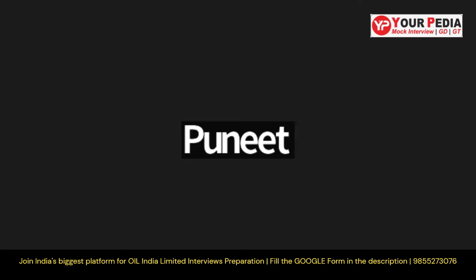Sir, first of all, I would see whether the voltage and current are within the permissible limits during the problematic condition. If they are, then I would tackle the problem, whatever is occurring. And if they are not, my first objective would be to disconnect it from the supply so that no power can be drawn by it. Then either repair the motor if it is possible then and there, otherwise replace the entire system.